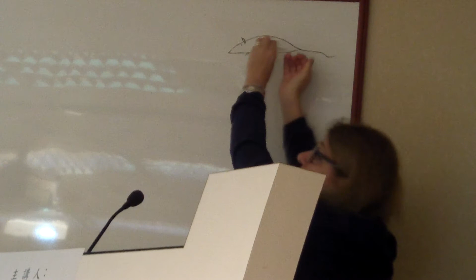But do not use a hypodermic needle and then try and get the sensor in, because it's different inside from the sheath, and you will quite likely damage the sensor. It's good for us if you damage the sensor, but bad for you. We don't want that, because you have to buy a new one, so it's more expensive. It's better if you use an angiocath. Okay. Any other questions so far? Okay.